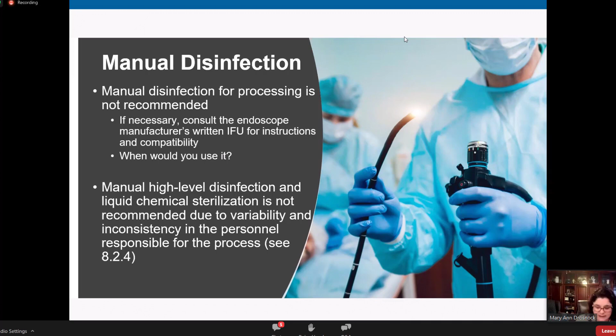And as I said at the beginning of the program, look at where your scopes are being reprocessed. This is going to really affect your off-site locations where they're doing manual soaking in the disinfectant. So it might be that they're soaking in OPA still, or they're soaking in a glutaraldehyde in a container with a lid, hopefully. That's no longer recommended for routine processing. So it's going to be a challenge. I know some people have space issues, and we know that it's a financial issue too, but this is something that we definitely want to get facilities moving to, this automated process. We're alleviating that variability and inconsistency that is going to happen anytime humans are involved. And like I said, there's just so much evidence out there to support moving to an automated system.